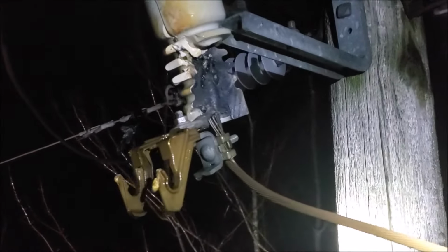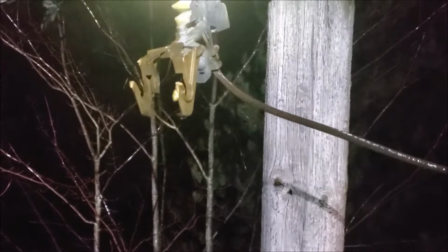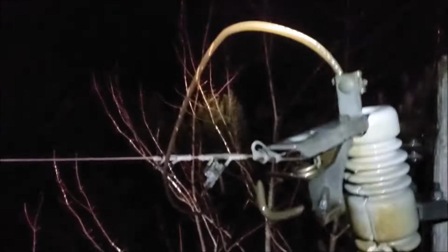So look at that. You can see on the pole, it wasn't going to ground that was causing the flashing. That was cross phasing. The 7200 volts in this phase, 7200 volts in that phase. The two of them don't mesh together. There's 12,470 volts between the top and bottom of that switch. You can see there it actually melted the copper.